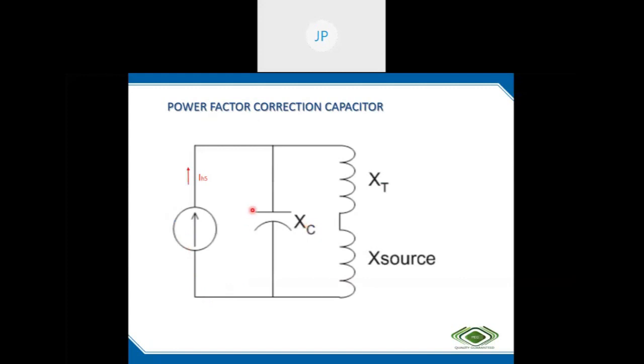This is the capacitor and we are injecting 300 amps. The current is dividing, and the division will be inversely proportional to its impedance. Xc is inversely proportional to frequency, 1 by 2 pi fC. So for harmonic components, the Xc will be very low, and XL is proportional to frequency, so the XL will be increasing accordingly.